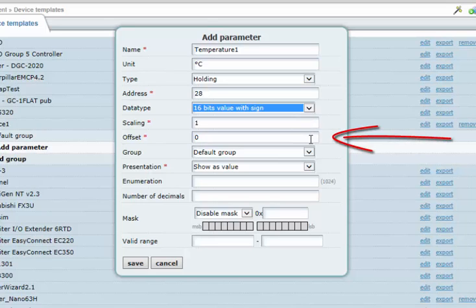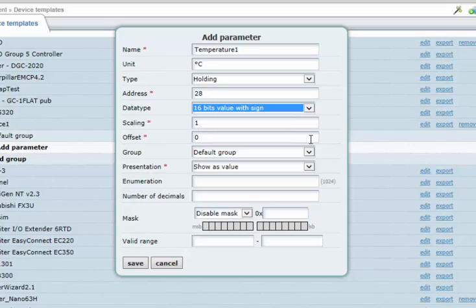An offset is another way to modify a value, and this is always applied after any scaling. The offset value is added to the register value before being presented, and also before it is written to a Modbus register.